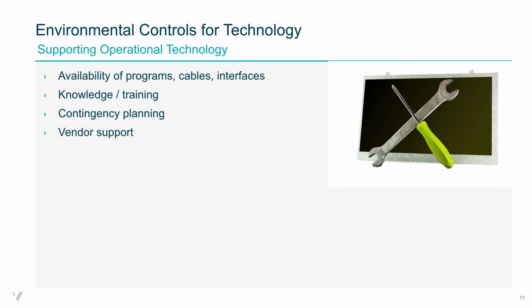So any cables, any adapters needed to affect that transfer. In the event of that system, from the case study in New Zealand, an ideal situation may have been a replacement board. The ideal situation would have been that the technology wasn't contaminated via oil from the engine room in the first place. However, if that had occurred, you need the ability for someone to swap that board out, put the new board in, and transfer the program in its current form, with any cables, adapters, and a suitable laptop or whatever is needed to allow that service to be reinstated quickly.